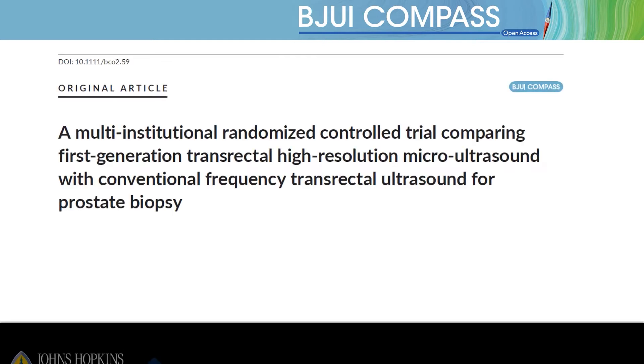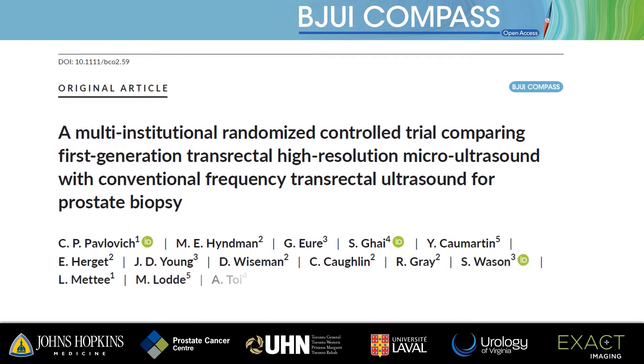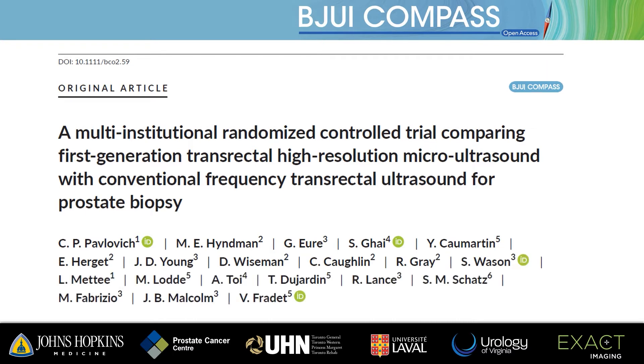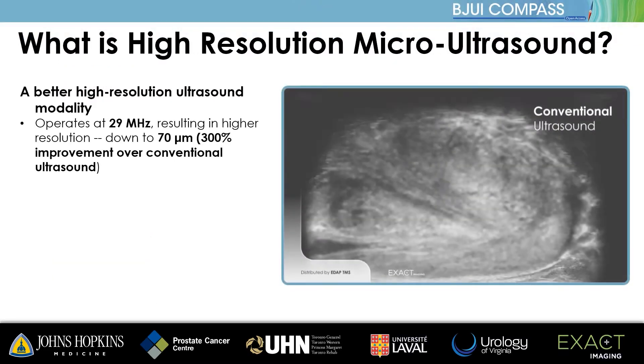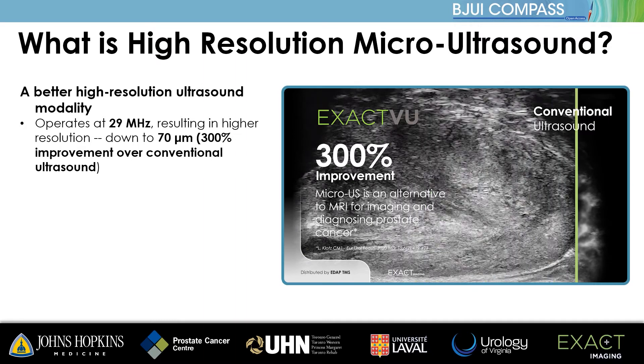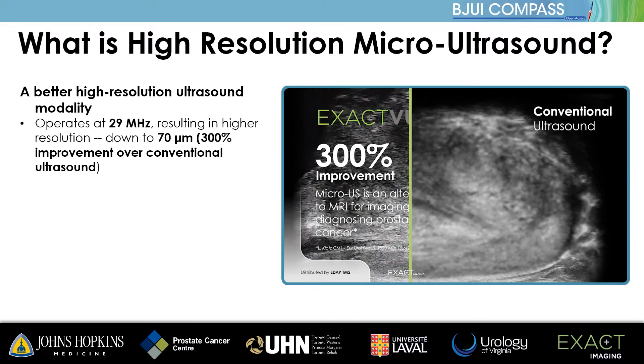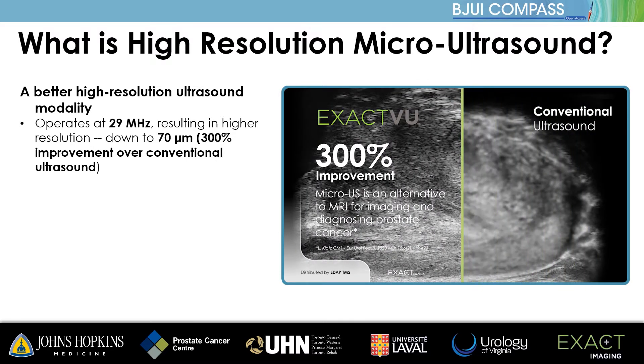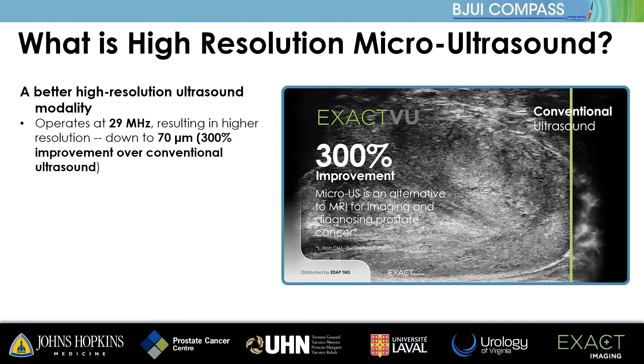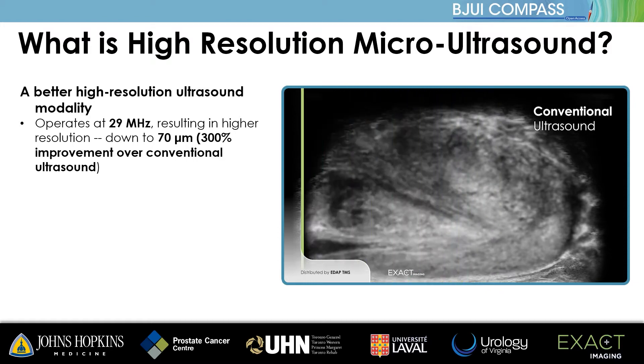Welcome. This is a video supplement to the first randomized controlled trial comparing 29 MHz microultrasound with conventional ultrasound for the detection of prostate cancer. Microultrasound operates at a higher frequency compared to conventional ultrasound, allowing it to image the prostate with much higher resolution. The 70 micron resolution of the ExactVu device is similar to the size of a normal prostatic duct, allowing visualization of disruptions in the normal tissue structure which are suspicious for cancer.